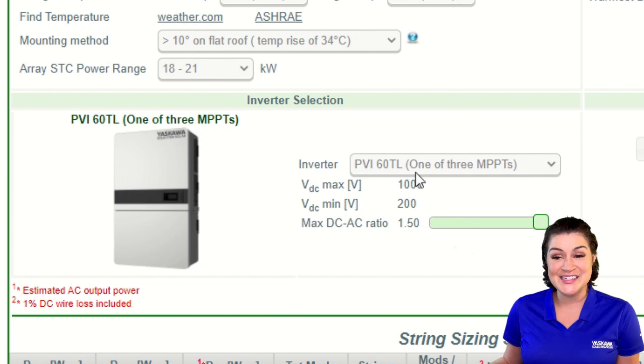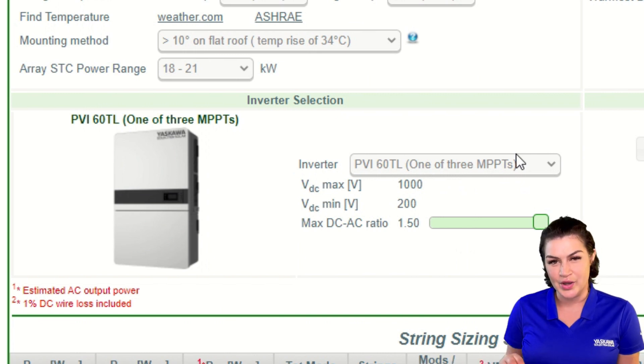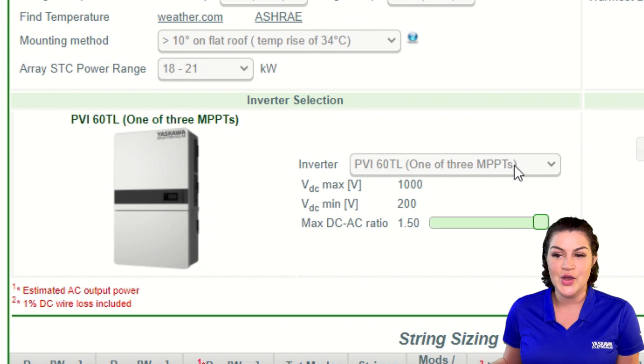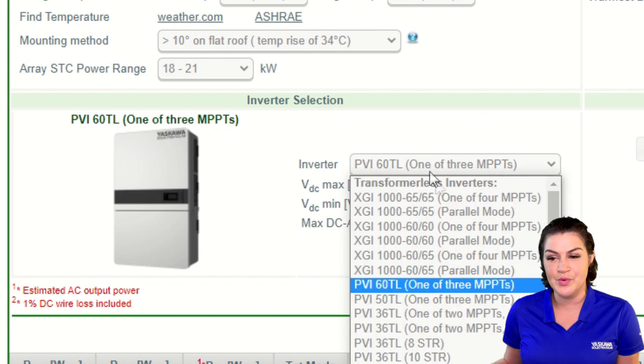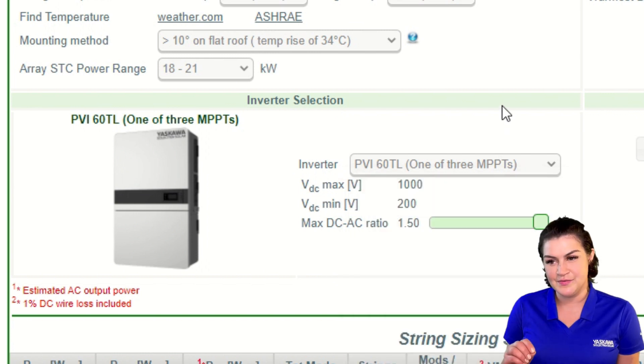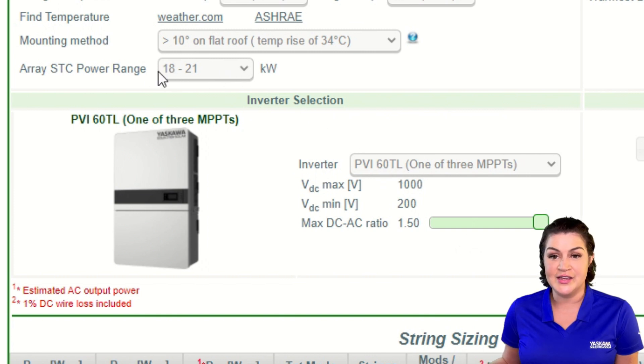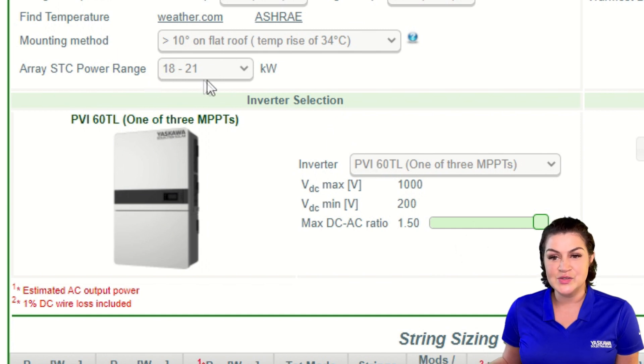Note that this PVI 60 TL says 'one of three MPPTs,' so we are going to be sizing just one of the three MPPTs. If you see one that says 'one of three' or 'one of two,' you're just sizing that specific input. This is a 60 kilowatt inverter, so each MPPT would be 20 kilowatts, and that's what this 18 to 21 kilowatt range is reflecting.